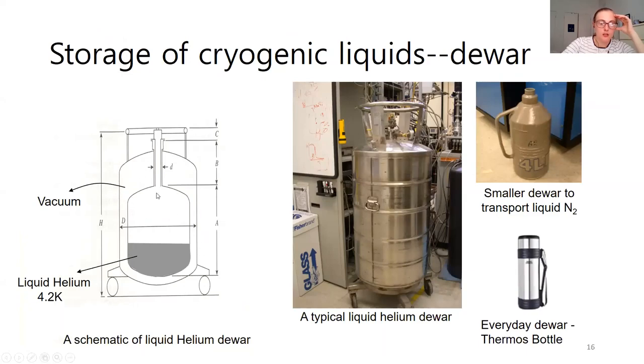These are stored in dewars where a dewar means that you have this vacuum area between the outside of the container and then where you're storing your cryogenic liquid. This is because vacuum has such a low thermal conductance that we don't have the issues of the outside of this being cold. It insulates the helium and keeps it in the liquid phase there if you have the pressure correct.